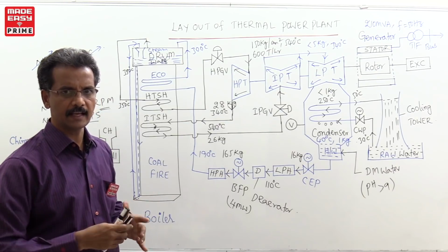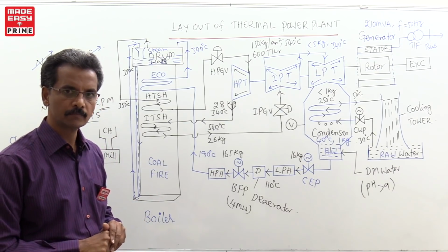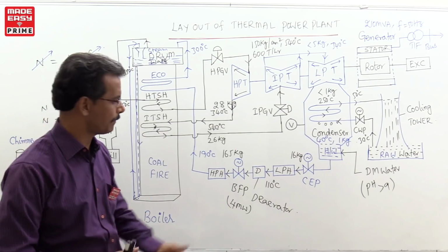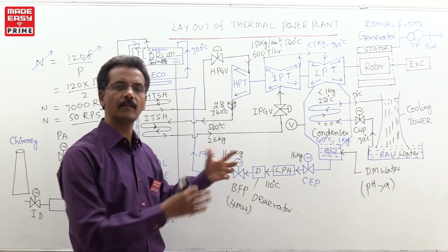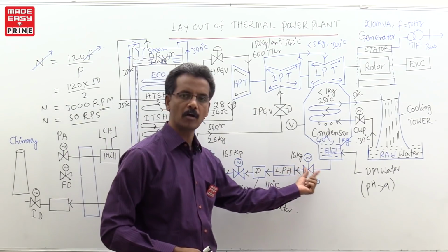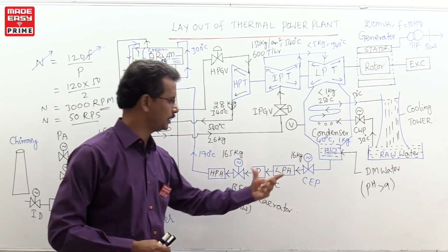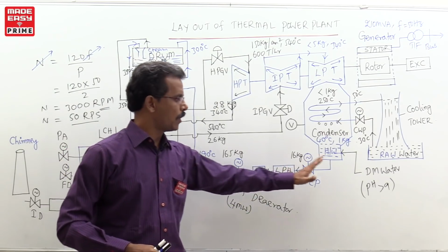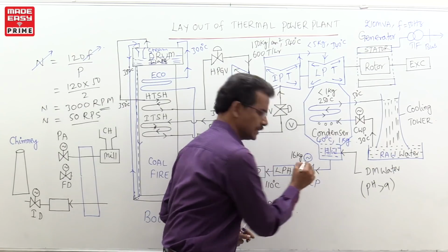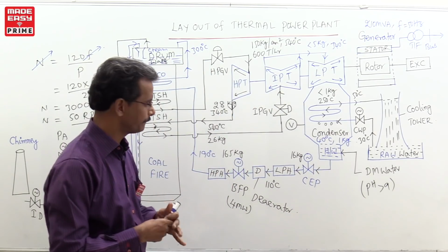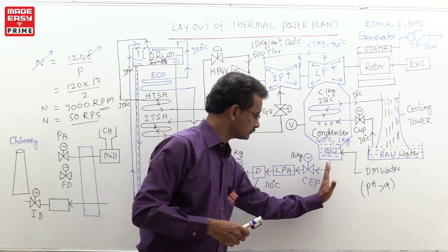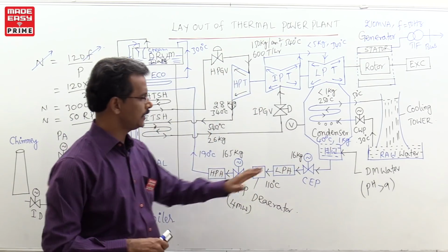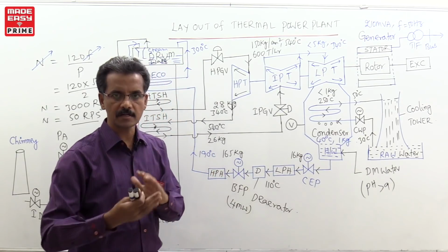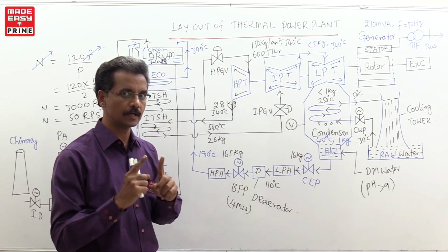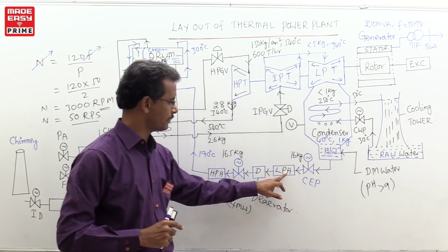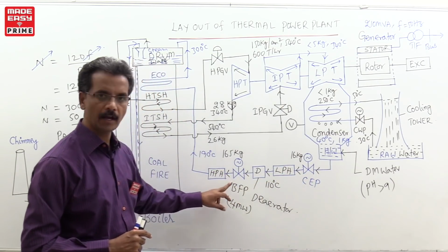You can imagine, in case of the Rankine cycle, especially for the mechanical students, you know better. So in this Rankine cycle, what are you having? You are having pumps. Basically, you can think of this as the boiler feed pump. Particularly, you are having a condensate extraction pump and a boiler feed pump. These are the two pumps, right? So the water coming from the hot well, I am repeating, just for your easy understanding, passes through different stages, and in these stages we are increasing the water pressure and water temperature for improvement of thermal efficiency, that you can remember, right? So condensate extraction pump, LP heaters and deaerator, boiler feed pump, HP heater.